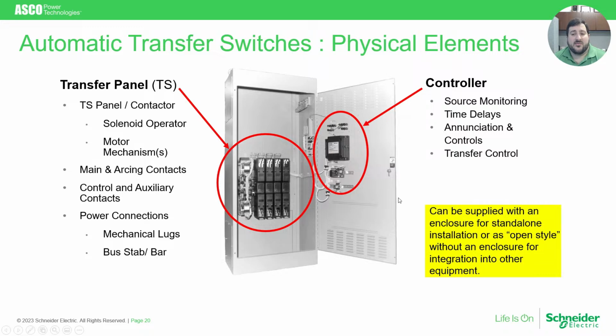So a transfer switch really is made up of three key areas. The one area is the controls, which are the brain of the equipment and govern the sensing, the sequence of operation, when should it transfer, the time delays, all that. Another part is the transfer switch itself, transfer panel, contactor. You may hear all those different terms. It is the same thing.